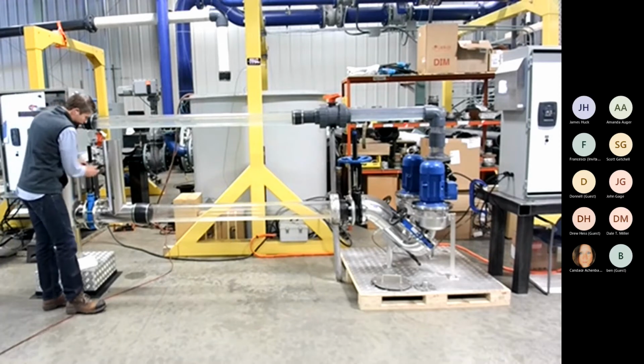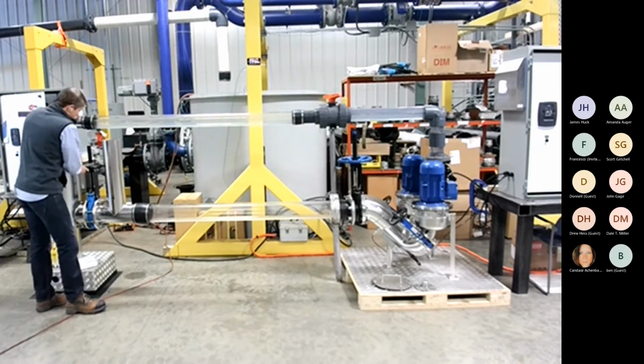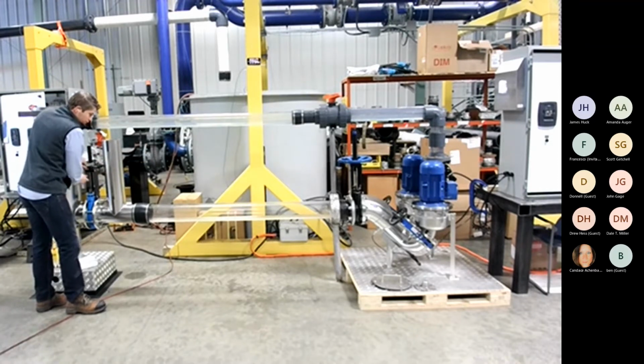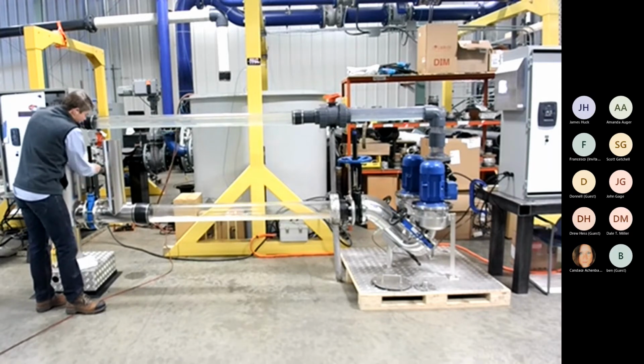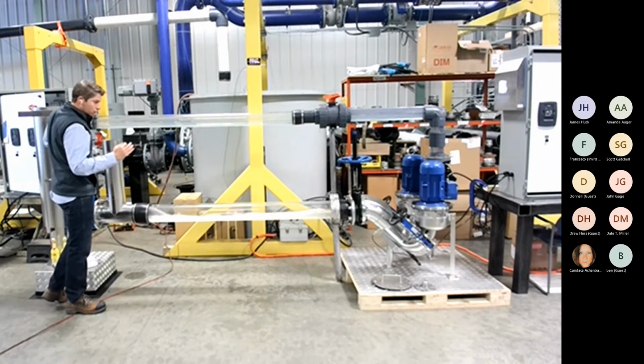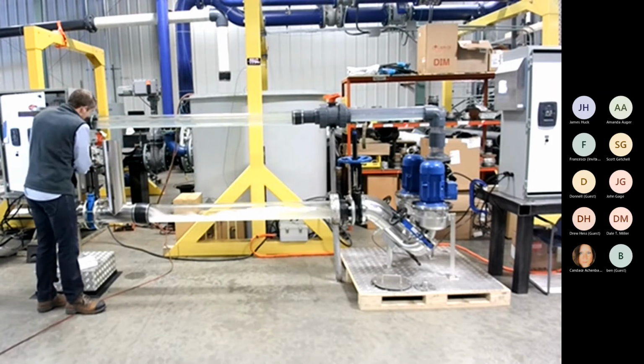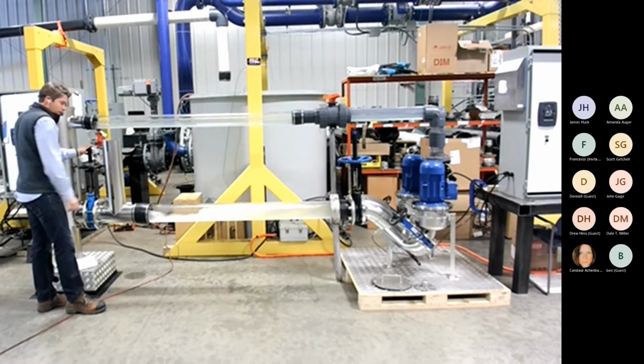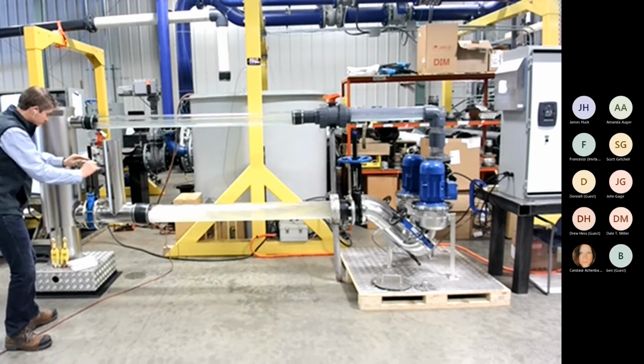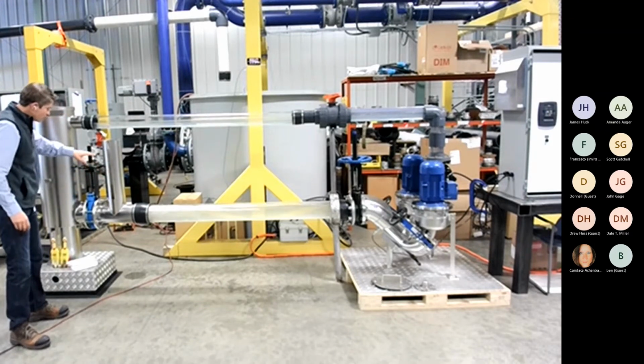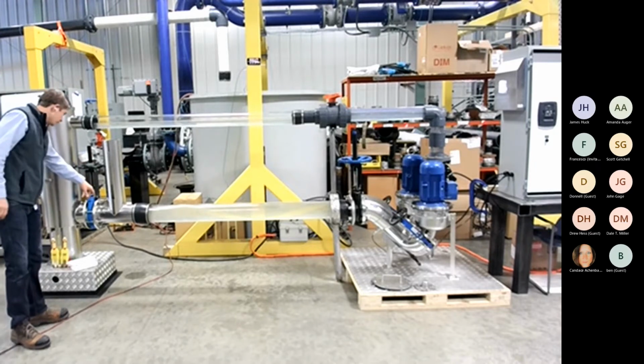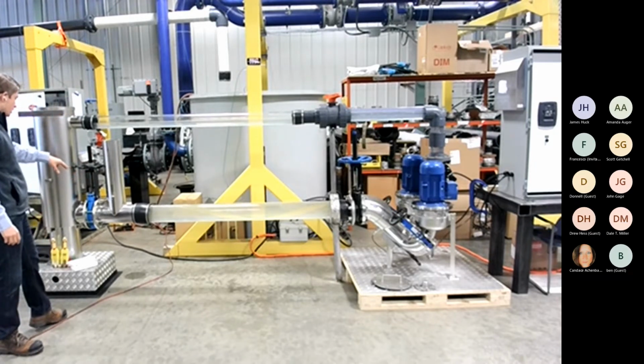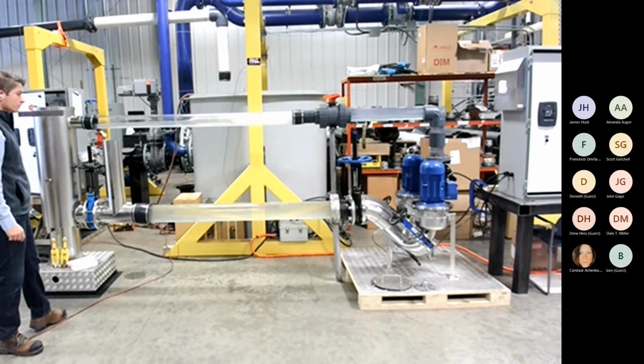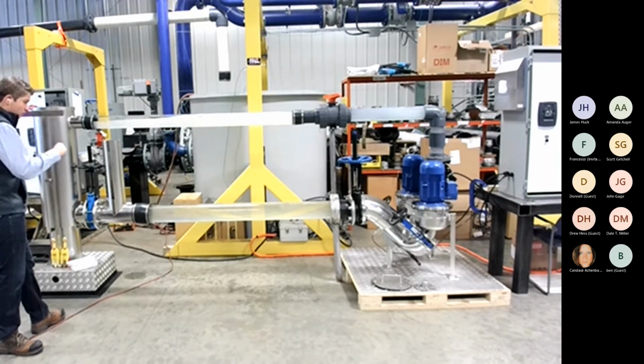So as I'm talking, I'm going to go ahead and crack it open because it's going to be in linear mode right now because it's turned off. It's going to sense the liquid pressure coming into the system. And if it can get to a point where it can regulate and pick a really low frequency, it's going to do that. It'll take it a couple times, maybe 3 or 4 times, to understand what flow rate is coming in. The system is not going to start until I get to the predefined height here. So it's about 20 inches. The system is going to go ahead and turn on right about now. There we go. The system is turned on, and now we're pumping.